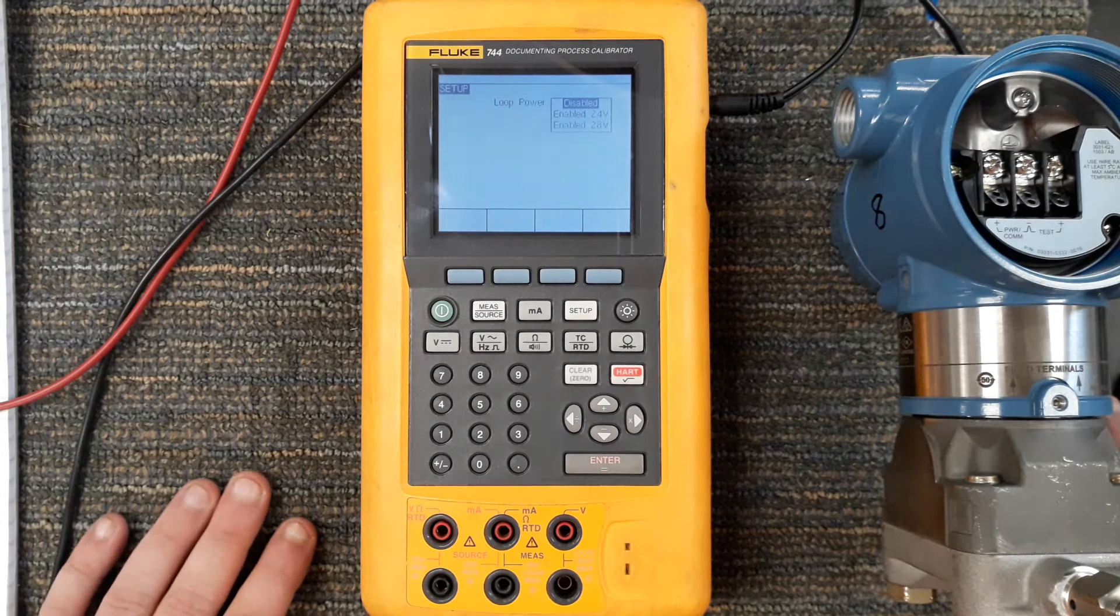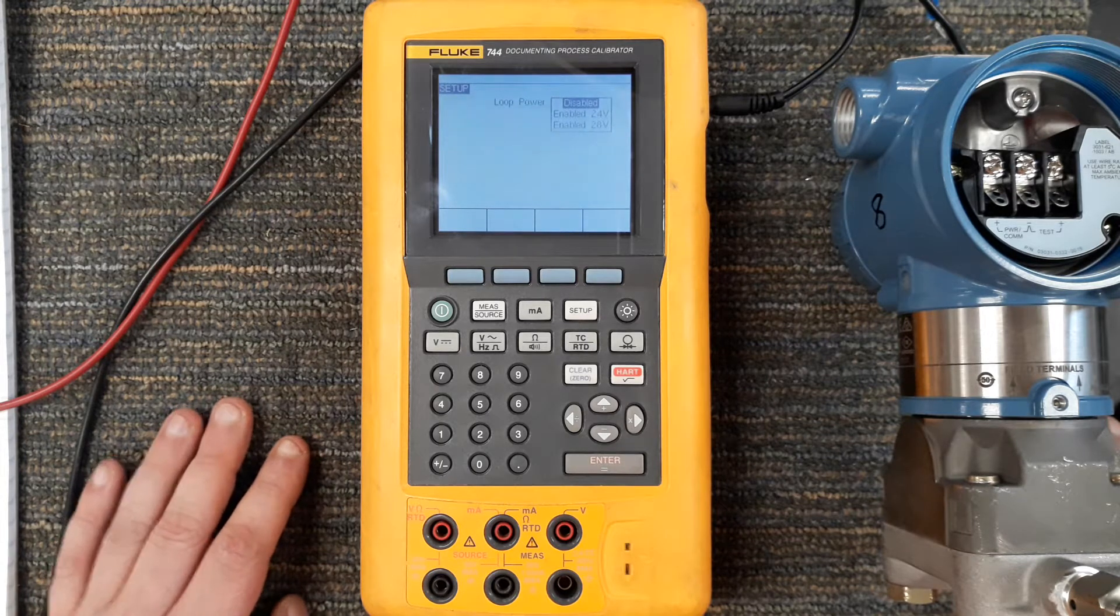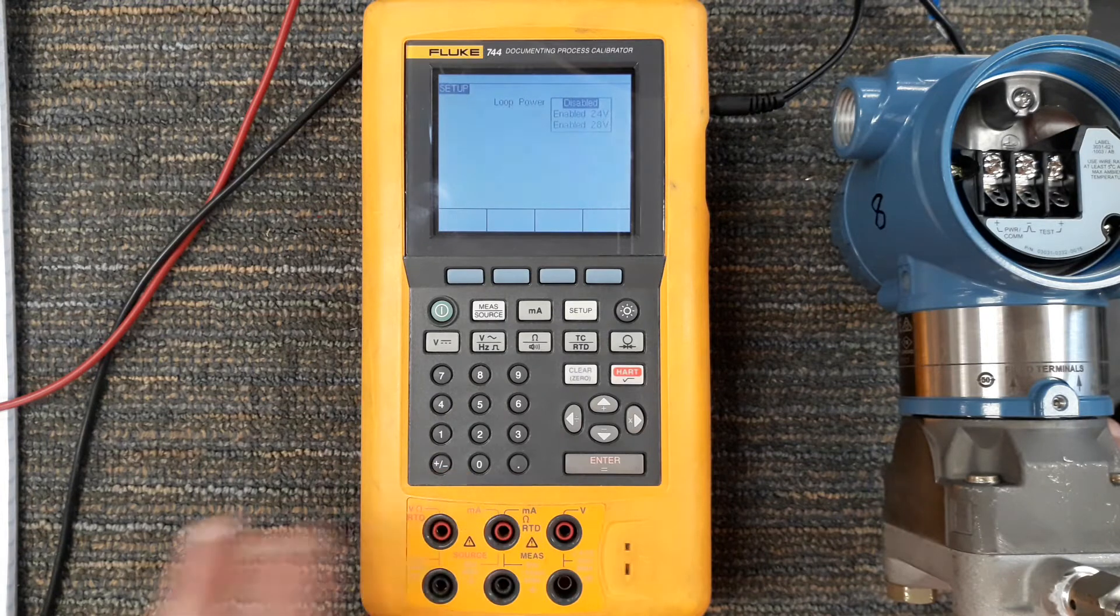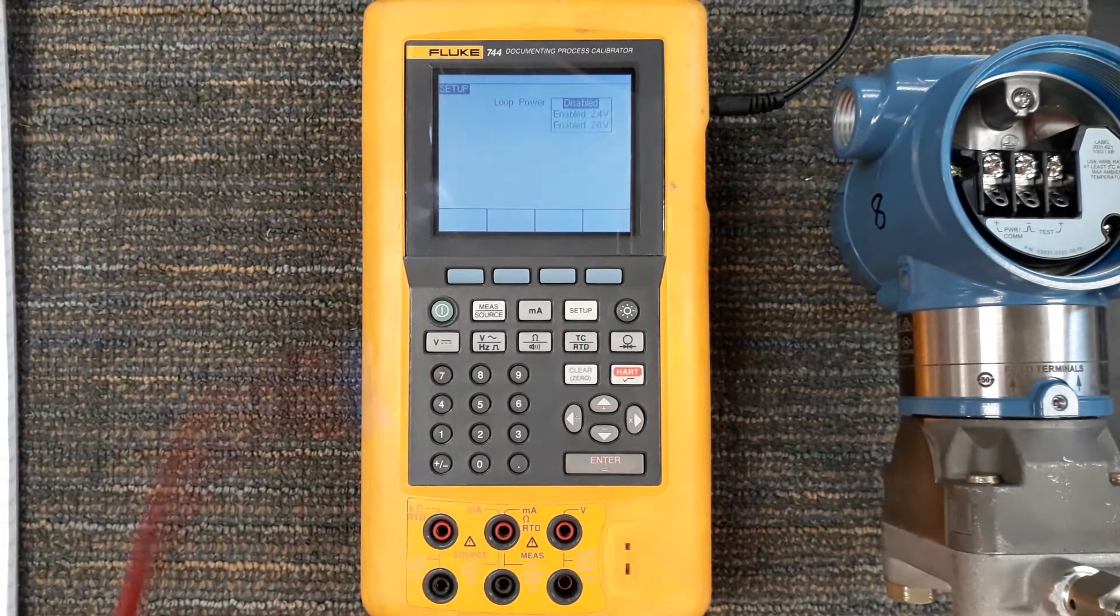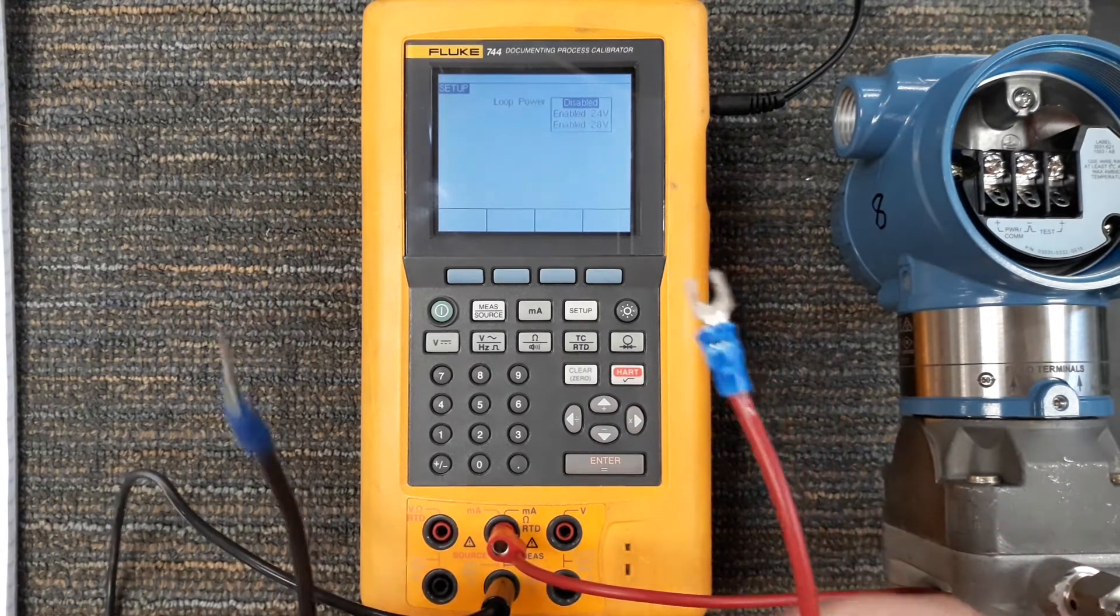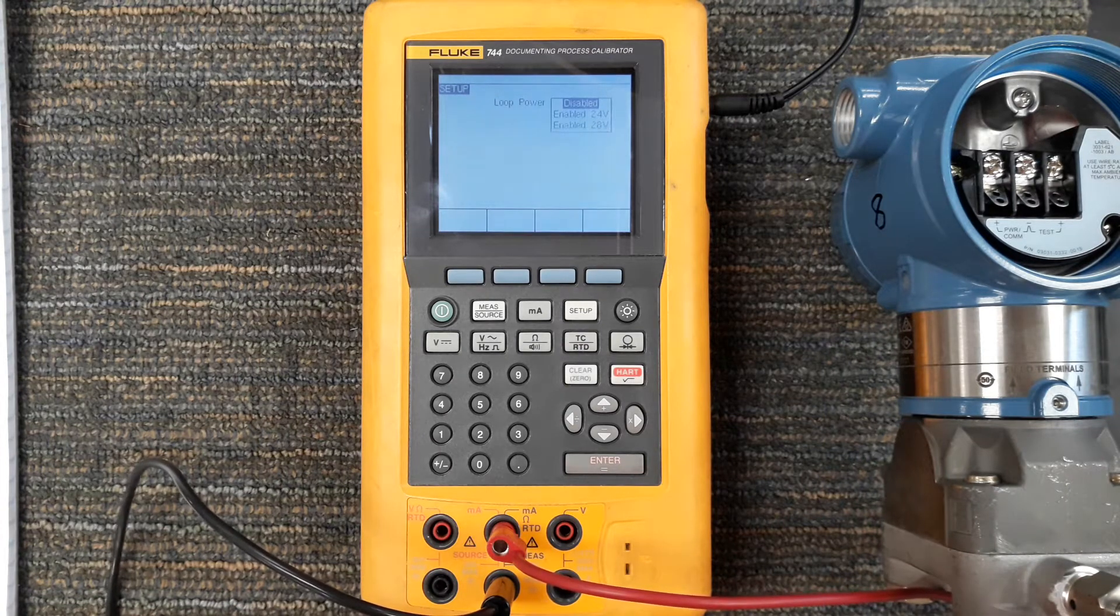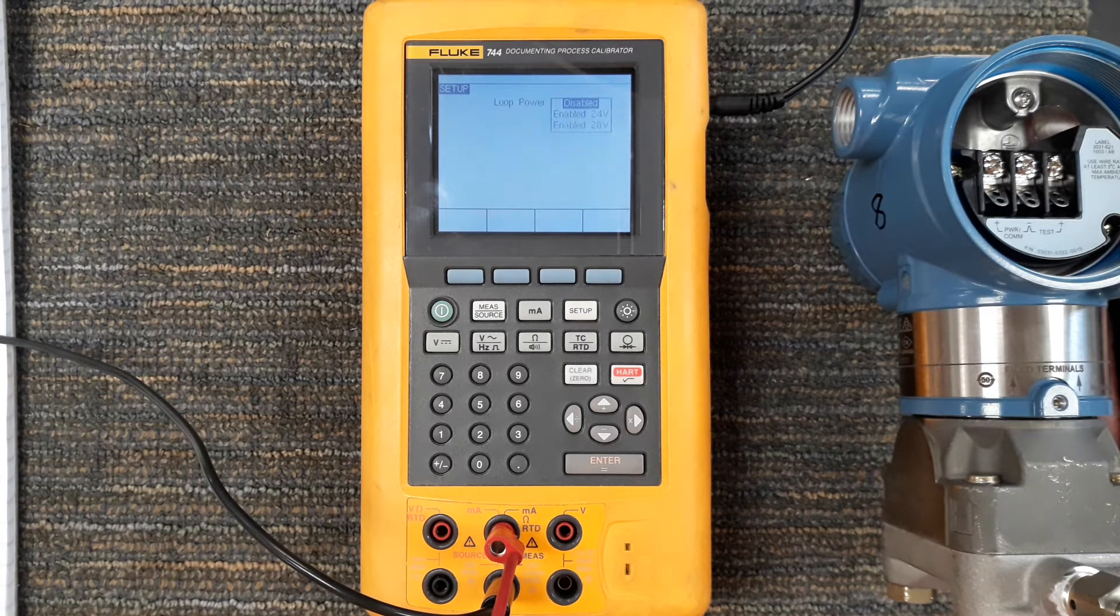What you're actually doing is sourcing loop power. Power is not just voltage, it also requires current. Hopefully your 1401, 1441, your instructors have given you a good clarification on the difference between voltage, current, and power. Voltage can be present by itself. If I just have two wires hooked up and they're not connected to anything, then there's no complete path for current to flow. If I were to enable the voltage right now or the loop power, I'd have voltage present but no current. At that point I wouldn't actually have power, I would only have voltage. Power requires voltage to be present and a complete path for current to flow, so power is current and voltage and that's actually the mathematical formula: voltage times current calculates your power.